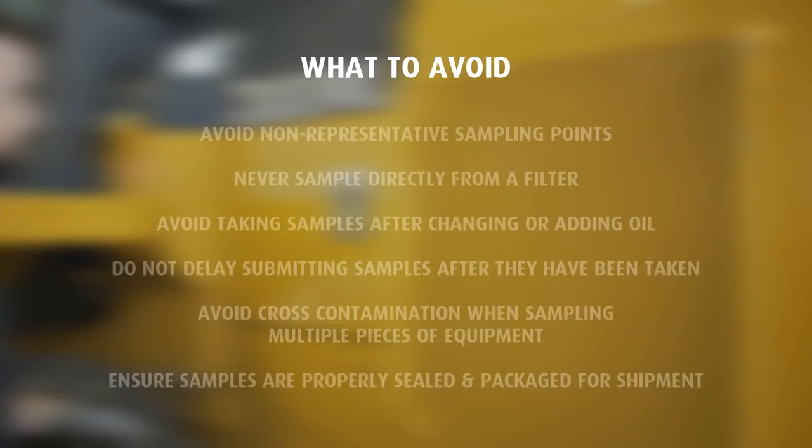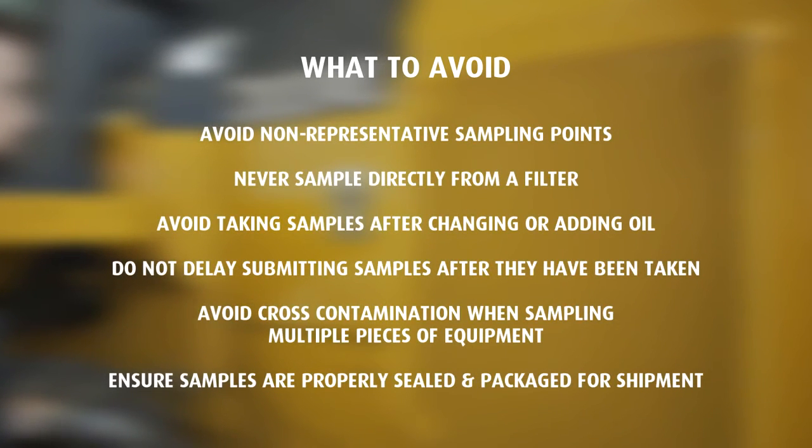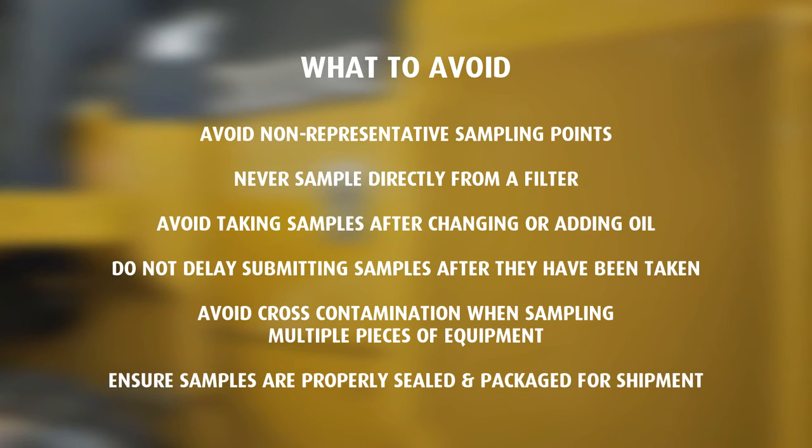Things to avoid when taking a sample. Avoid non-representative sampling points. Never sample directly from a filter. Avoid taking samples after changing or adding fresh oil. Do not delay submitting samples after they have been taken. Avoid cross-contamination when sampling multiple pieces of equipment.